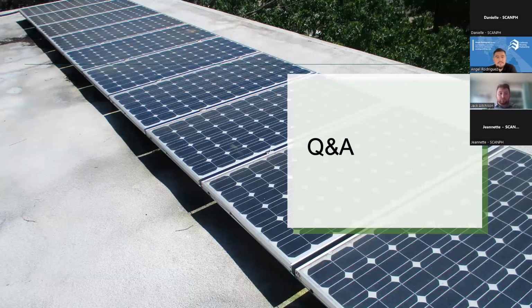The next question we have is, are there increased space requirements needed for replacing a gas water heater with heat pump water heaters? Most gas water heaters are in existing closets. Great question. Thinking about residential water heaters, you're right. In multifamily, the gas water heaters are typically in a small closet. Heat pump water heaters are going to be physically larger because they have that heat pump component, and because they typically require more storage since the recovery is lower. So finding a location to install those can be difficult. However, what we found is that you can typically physically fit them, and they are making thinner, more multifamily-style heat pump water heaters that fit in those small closets.